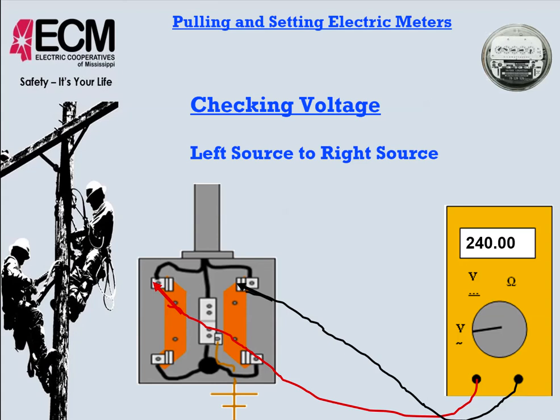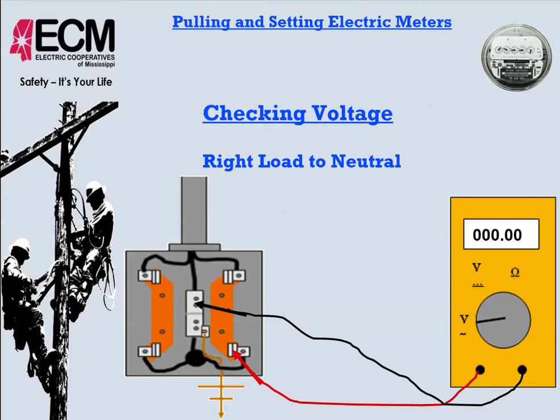Okay, so the bottom side of the meter base is equally as important to test as the top, but however it is one that is often skipped over, and it should not be. We should make sure that we're testing the bottom as well. There's three things here. One thing is that it's not hot, it's not grounded, and the load is not tied together. Now, the load not being tied together is very difficult to do unless we can get the load side breakers turned off or disconnected. If not, this is going to be almost impossible.